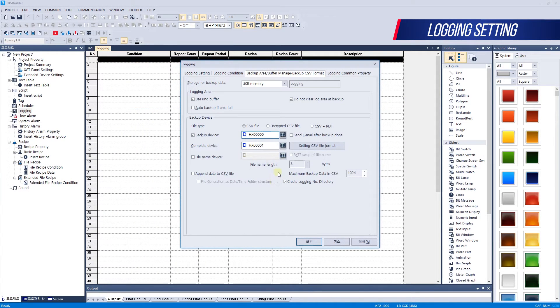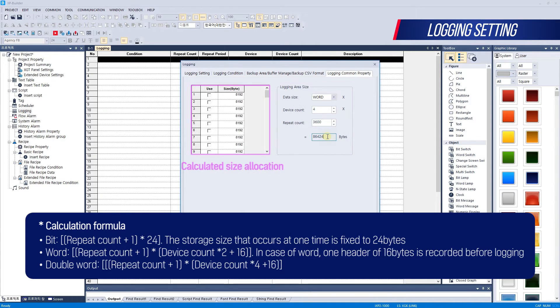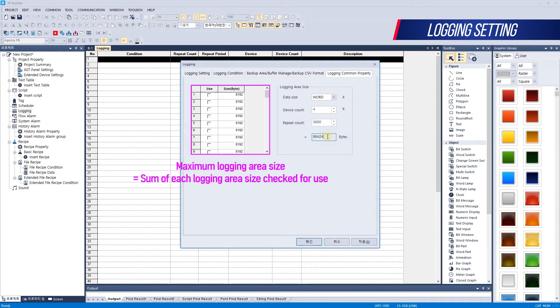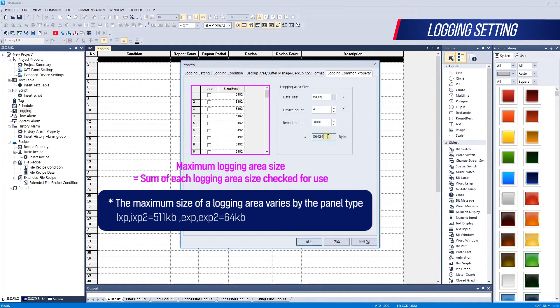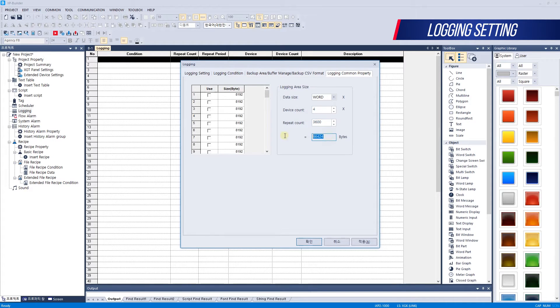You can set the size of the storage area for each logging. Calculate the logging size on the right, check whether it is used or not, and assign the calculated size to the left logging size. The sum of all loggings checked for use on the left will be the logging maximum size. The maximum size of the overall logging varies by HMI model. Let's calculate the size of the data stored in NVRAM for an hour. We set four devices, logged every one second — 3,600 times per hour. Check the calculated size, set it to the left size, and check whether it is enabled or disabled.